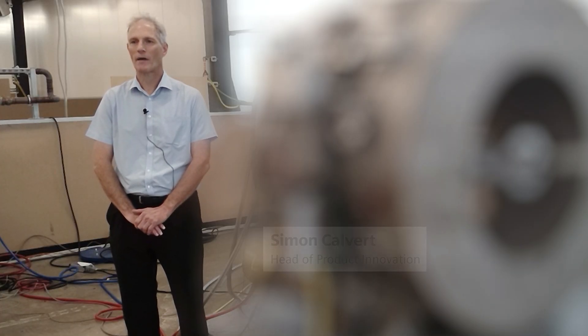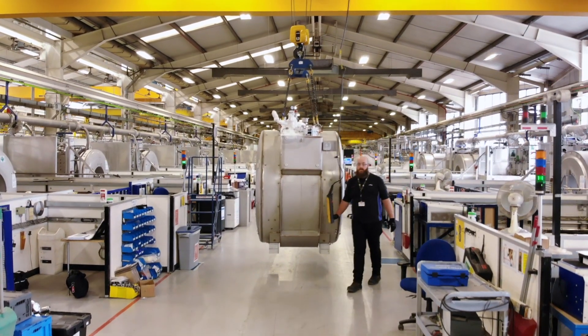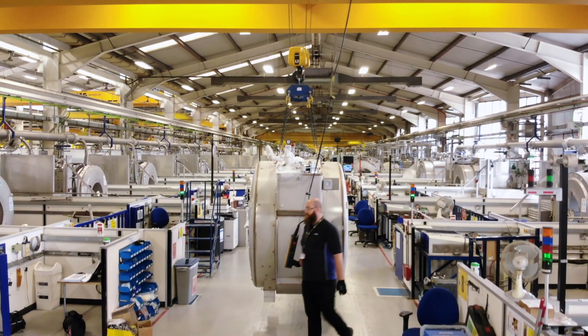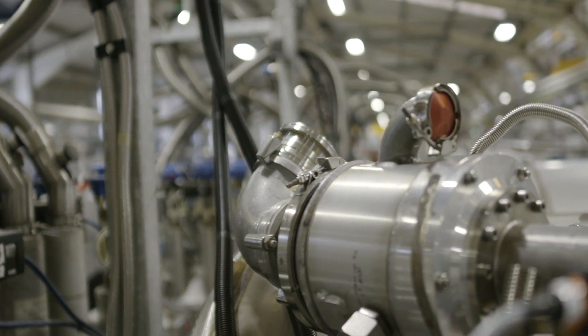We had a vision of producing an MRI magnet similar in size to a domestic refrigerator, just requiring a simple power plug — a plug-and-play MRI magnet with all operational infrastructure integrated. We realised a magnet cooled by a sealed helium system containing just 0.7 litres of liquid helium. A key focus of the magnet design was to minimise weight, ensuring the magnet can be cooled down quickly using only its own refrigerator.